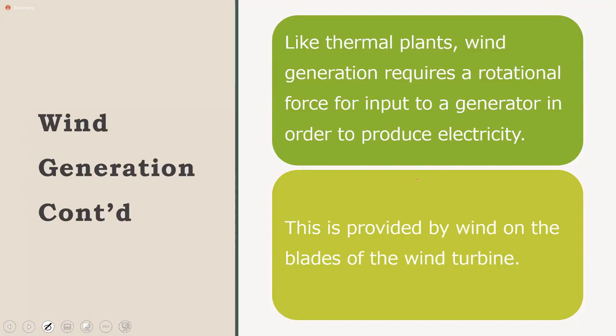But you have variable wind speed generators. You have wind turbines that are going to be using synchronous machines or induction machines. If it's induction, then where is the VAR support coming from? Because it would require VARs to operate that induction generator. So these are considerations that will have to be made when we're talking about integration.